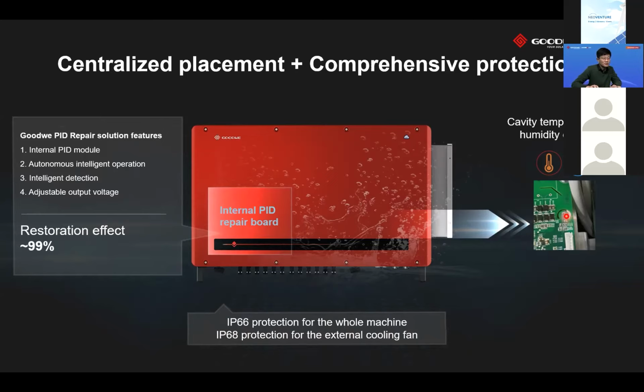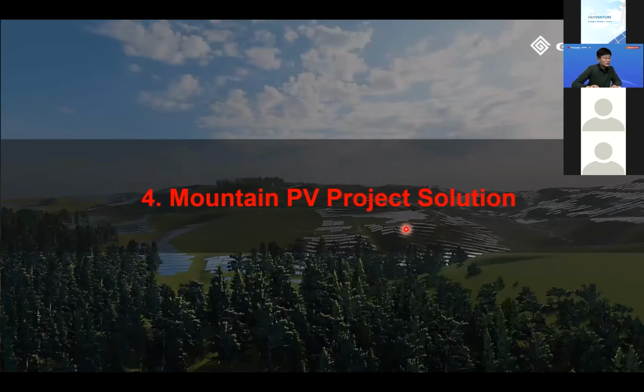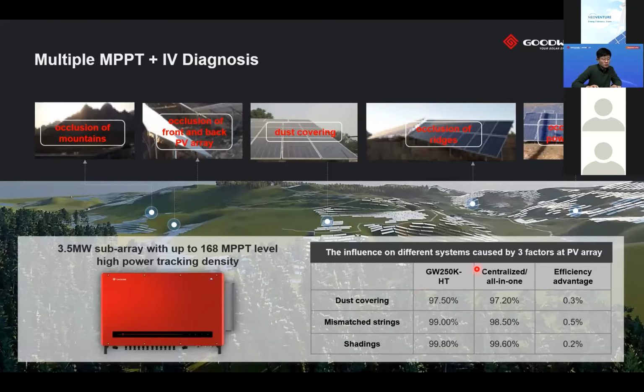And we also integrate the humidity detection in our inverter. Compared with traditional centralized PV inverters, our string inverters, HT products, have more and more MPPT units. With the numbers advantage of MPPT units, even with dust covering, string mismatch, or shadings, which are very common phenomena in mountain PV projects, we still get higher efficiency than traditional central inverters.